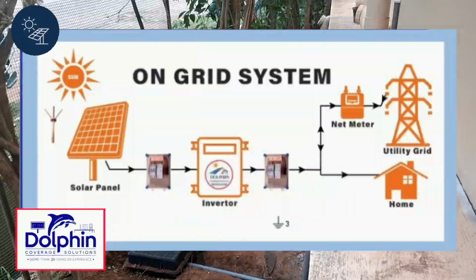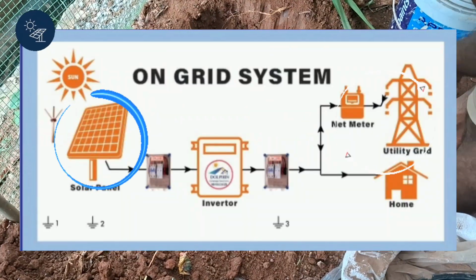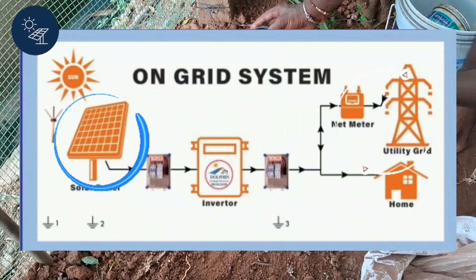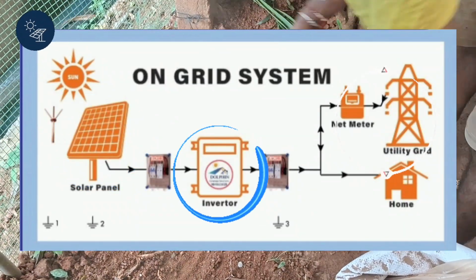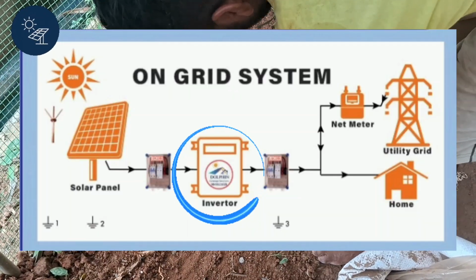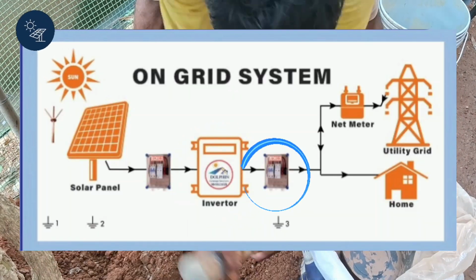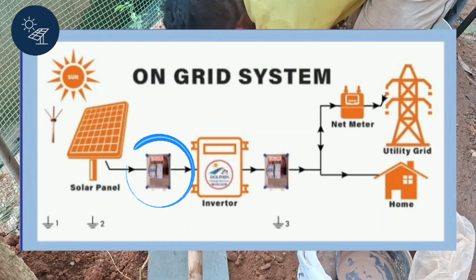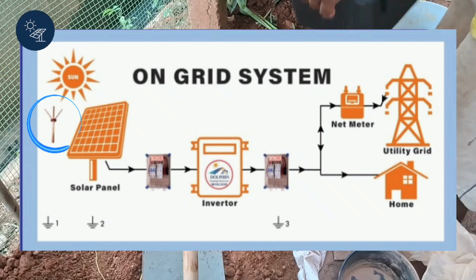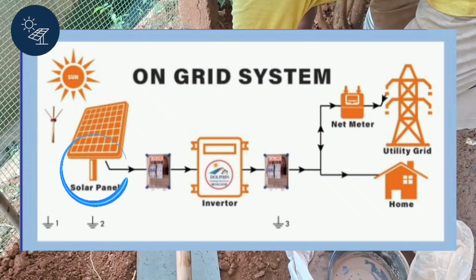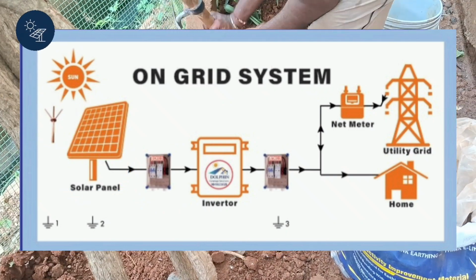Identification of components to be earthed. This includes solar panel frames and mounting structures, like the DC earthing; the inverter chassis, this is for AC earthing; AC distribution boxes, DC distribution boxes, the lightning arrestor if installed, and any other exposed metallic parts of the system.